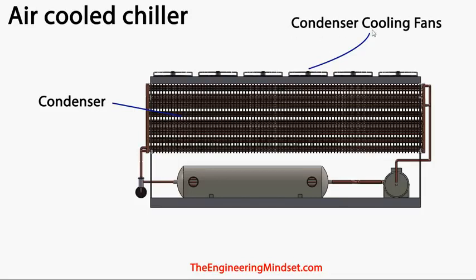And obviously, as we saw earlier, the condenser cooling fans are going to be pulling air. You can see all the way through this one now. So these fans will be pulling air across these hot pipes, and that will be sucking the air away and pushing that out into the ambient atmosphere.